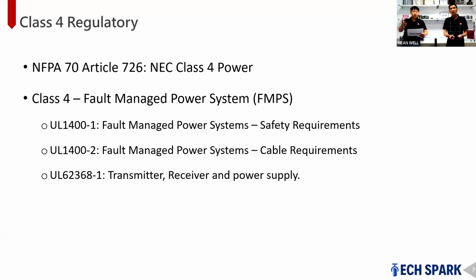So let me just reiterate that to see that I understand it correctly. So the components, like the power supplies, the transmitter receivers that make up the fault managed power systems, those are evaluated to the UL 62368-1 safety standard. Correct. And then the whole system, the system as a whole, would be evaluated to UL 1400. So if a customer asks us if Mean Well we can do UL 1400 on our power supplies, I think the answer would be no, right? Because it's evaluating the whole system. Correct. I see, yeah, I see.